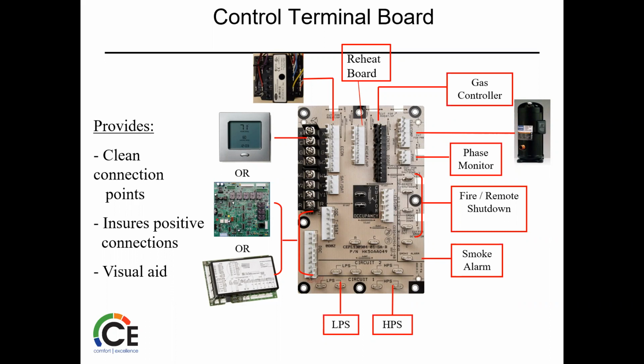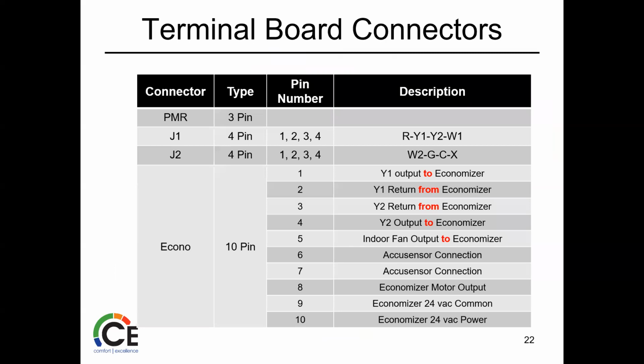Reheat board will have a Molex that goes to that board if we need it. Again, the main control board Molex, for this is a gas unit, so that's going to go to the gas IGC board. Phase monitor if it needs, compressor terminal, fire and smoke shutdowns. Again, if we need them, and you can see there's jumpers to cut if you're wiring any of those up. And then of course, low and high pressure switches.